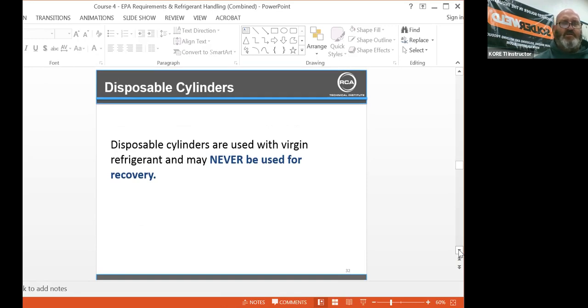Disposable cylinders are used with virgin refrigerant and must never be used for recovery. Have you guys ever seen the top of the little disposable cylinder? It's got that little top. That's actually a little pressure relief. We do not want to use them. They're not designed for it.